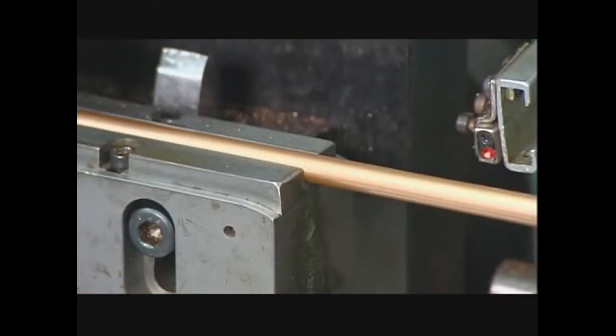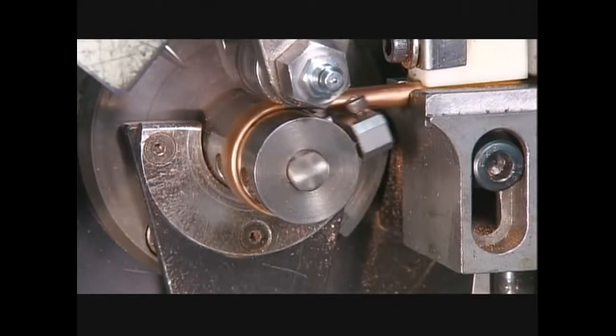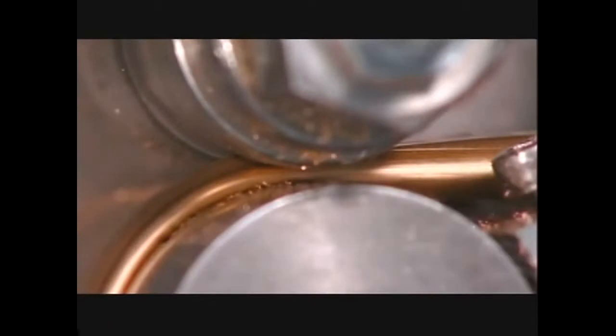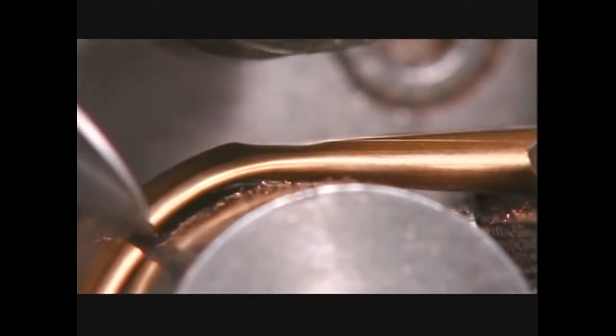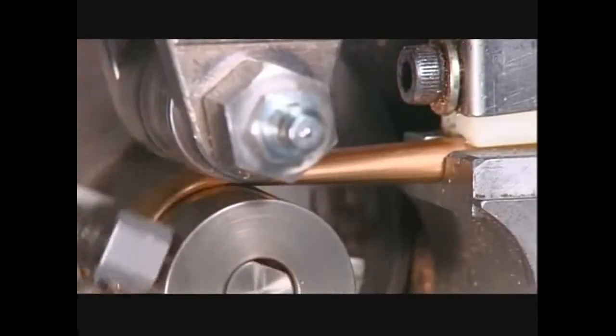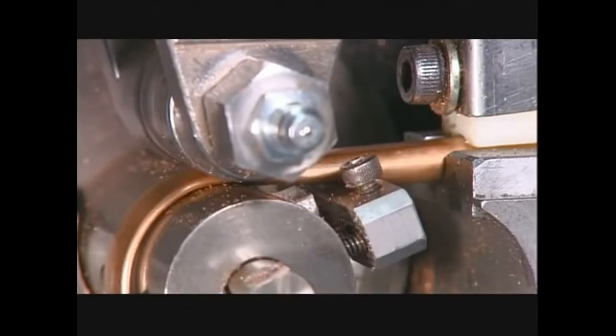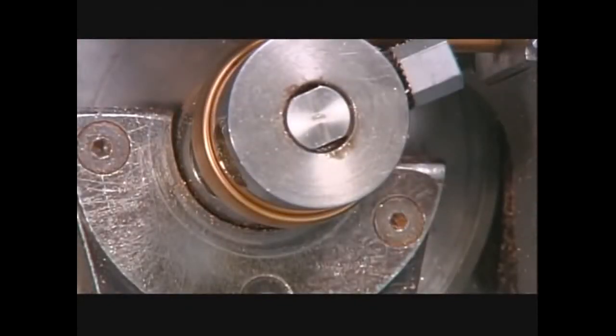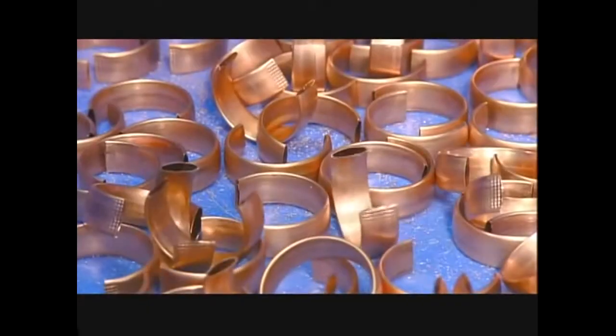Then a worker puts a copper tube into a bending machine that bends, cuts, and flattens sections of the tube. The amount of flattening and bending determines the pressure range the gauge can measure. Each piece becomes a pressure sensing tube known as a bourdon tube.